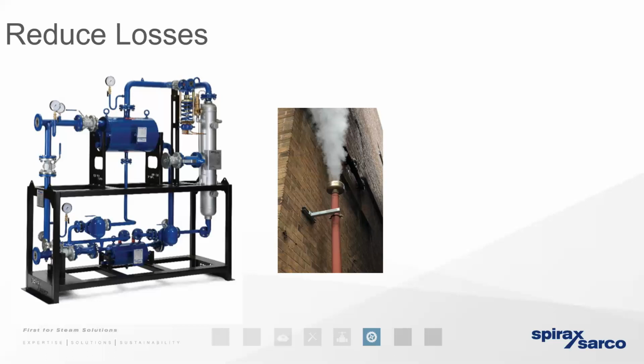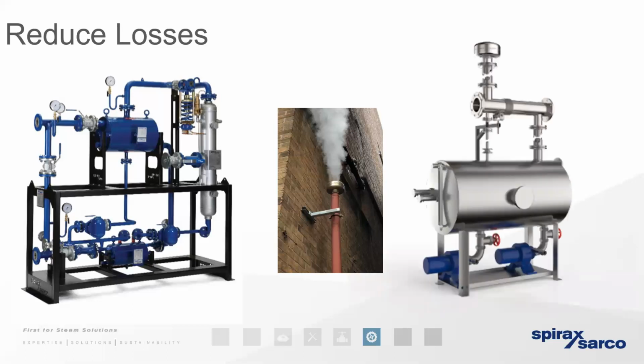And even if we've got flash steam escaping from the top of the condensate receiver, remember, we need to vent flash steam away at this point in order to protect the pumps from cavitation and to protect against any overpressure of condensate on the liquid side of the distribution network. Even if we fit a very simple exhaust vent condenser in the vent, it means we can at least condense as much of the flash steam as we can before it escapes to atmosphere. And if we're condensing a significant amount of that flash steam, we're increasing the percentage of condensate return. It helps us to move towards that net zero loss system that we were speaking about.